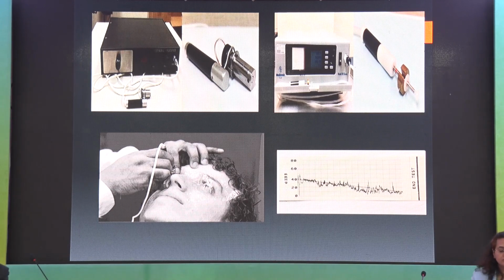On the other hand, once you get a good graph, which is a gentle downward slope from the initial IOP reading to the final IOP reading, and these minor small oscillations are due to the ocular pulse, you draw a line through the graph and have a slope. Nowadays we have better algorithms with second order polynomial equations that are used. Otherwise, in earlier days, Dr. Grant used to mathematically calculate it with his formulas.